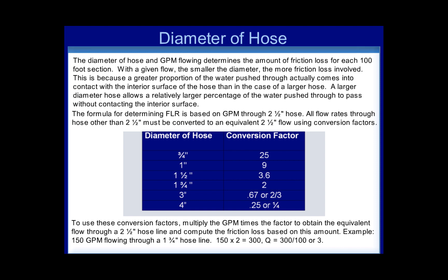Let's look at an example. If you have 150 GPM flowing through an inch and three quarter hose line, first you would take 150 and multiply it by 2, which equals 300. Q would then equal 300 divided by 100, or simply 3.